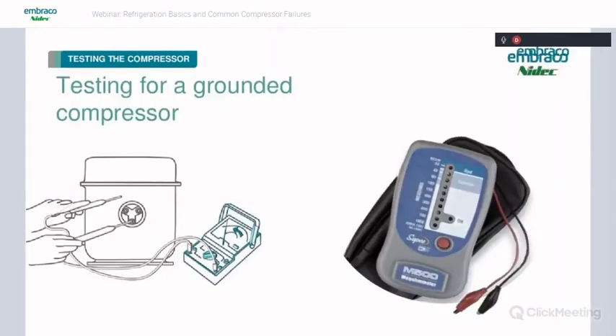So the second test, basically, we call it testing for a grounded compressor. What you're really doing is you're reading the condition of the insulation around the windings. A lot of people like to use their multimeter for this, but it's not recommended. It's recommended to use a megohm meter. The reason for this is this meter is going to put a very high electrical load on the windings, and it's going to read resistance in millions of ohms or megohms. And this is going to really test that insulation out. It's going to put a very high load on the windings and test that insulation out and read for minute leakages of current to the compressor body.